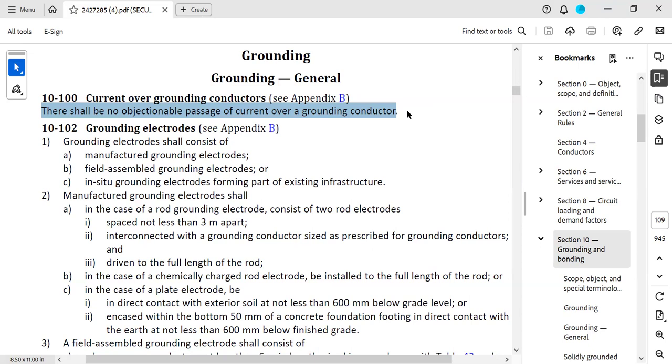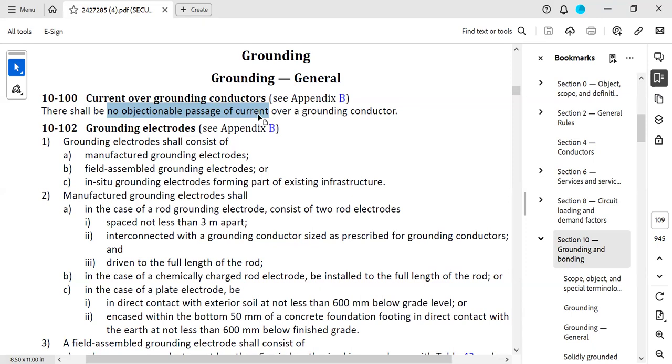There has to be no objectionable passage of current during normal operation. If current were to flow in that system during normal operation, there would be voltage differences between the points in the systems, and those are called ground loops. So you have to design this system so that your grounding conductors don't cause ground loops.